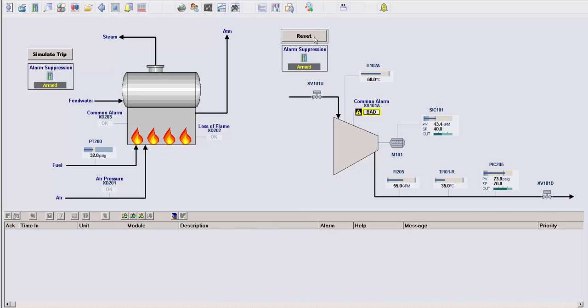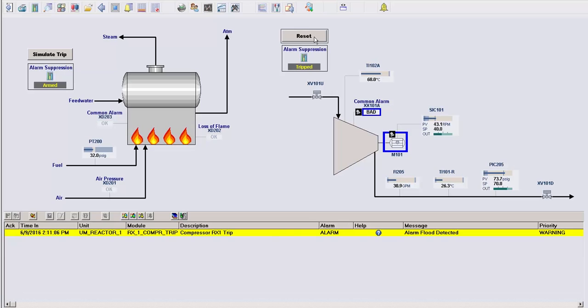So let me show you this module in action. When I have the logic armed and simulate a trip, once the trigger condition becomes true, all of the alarms in the list are suppressed and we get a common alarm in the banner.